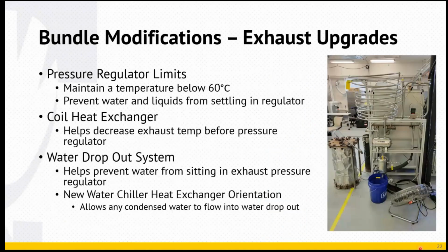With sending so much more mass into it, we also had to upgrade the exhaust so we could get all that mass back out. Most of this was driven by the pressure regulator, which has limits on temperature — it can't go above 60 degrees Celsius, because that's what it's tuned for and what AliCat recommends.